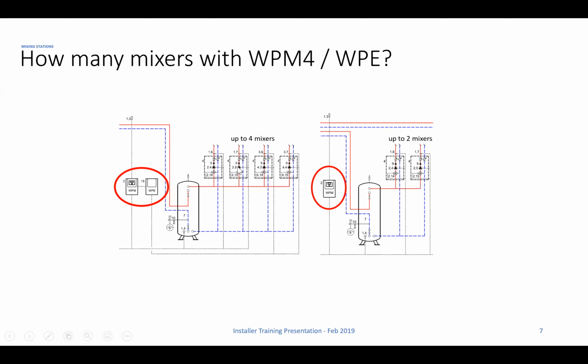So for example, we're looking for mixed circuits here. That's a fan coil unit, radiators and 2 of underfloor. The fan coil unit obviously can be set for fixed temperature, 7 degrees. The radiators can be turned off and the 2 underfloor can be run on dew point managed mode. So we can select the mode per heating/cooling circuit. Now, obviously important to remember, a WPM can do 1 direct circuit and 2 mixers, and the WPE, which is the heat pump manager extension, can do another 2 mixed circuits. So we can effectively do 5 circuits altogether, all pump controlled.